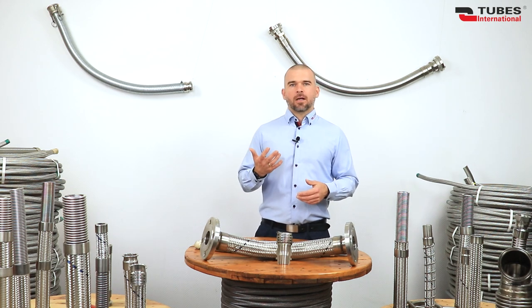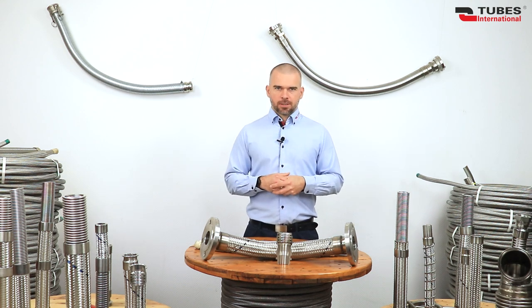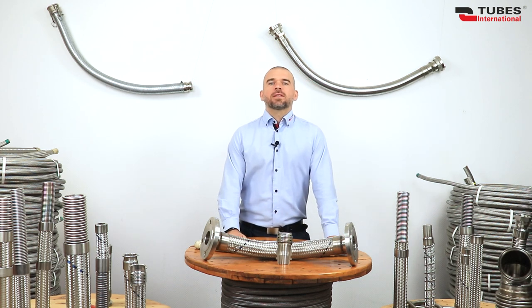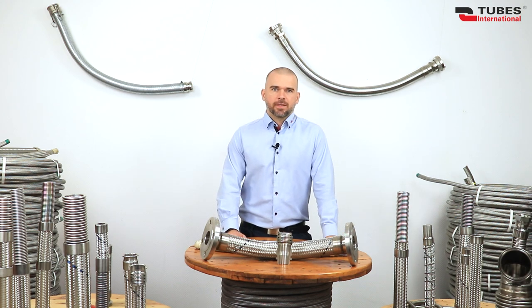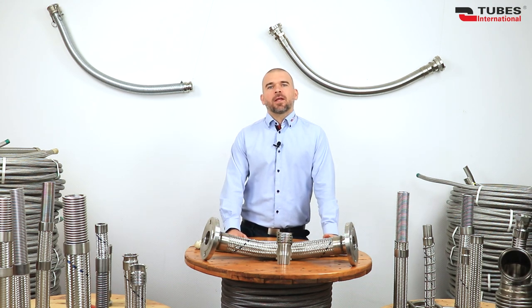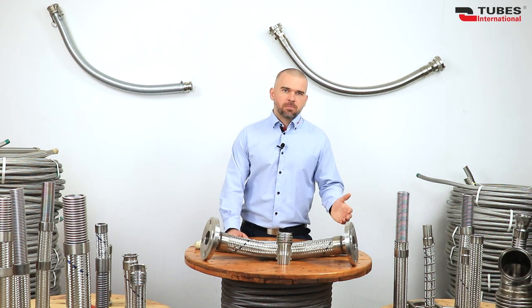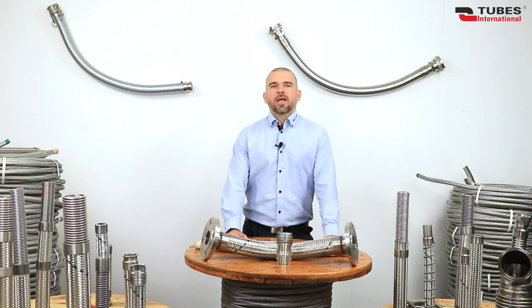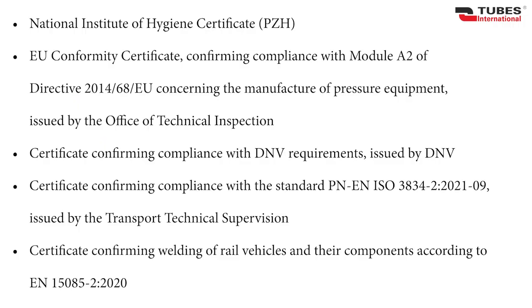An interesting fact is that metal hoses can also be used in the food and pharmaceutical industry — for water, steam, and liquid food production. Hoses of this type are most often finished with sanitary-type fittings made of stainless steel, for example DIN, SMS, Tri-Clamp. If you want to clean a hose using the CIP method without dismantling, remember to choose a hose with a wide corrugation pitch. The welding of the ends is carried out using a special hygienic welding method, and these hoses have a special certificate for transporting drinking water.